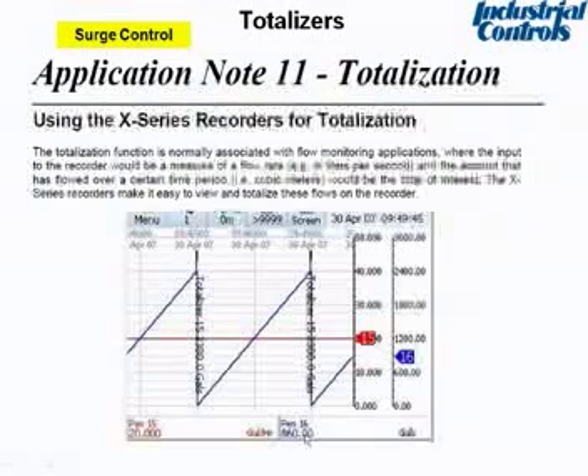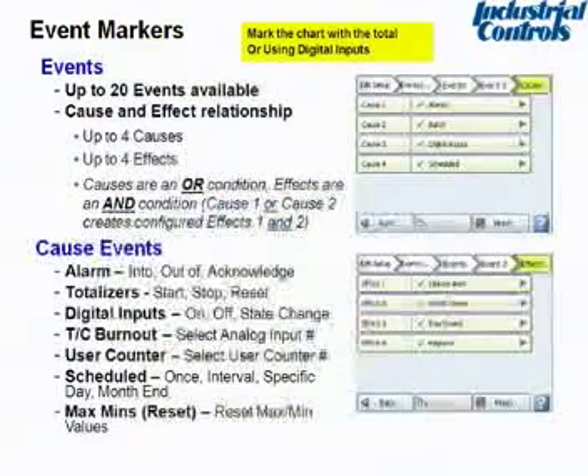And in this particular operation, we actually did something called a surge total. So by using the math capabilities and events, the customer wanted to have a separate totalizer that would only totalize when the flow rate went above 80% of the span. So we had two totalizers, one the running totalizer and two the surge totalizer, and that's how this particular customer was billing their customers. They billed them extra when they were in the surge category.